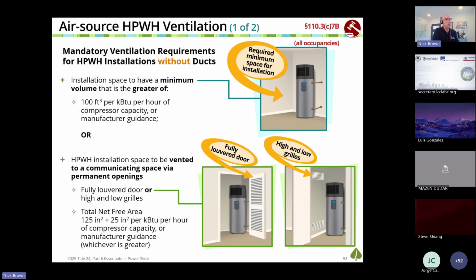You can either put your heat pump water heater in a large enough space, 100 cubic feet per kBTU per hour of the compressor. By the way, I haven't seen a lot of manufacturers who publish the compressor capacity of their heat pump water heaters, but most are 4,000 BTUs per hour, the typical 240 volt, 30 amp heat pump water heaters. So that would mean 400 cubic feet. By the way, it's the greater of the manufacturer's recommendation and this guideline. So if the manufacturer says you need 750 cubic feet, and that's bigger than this calculation, that's the one that matters.